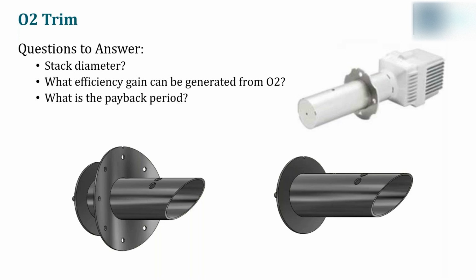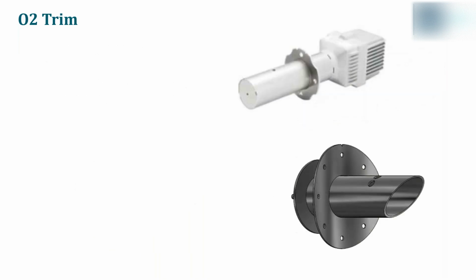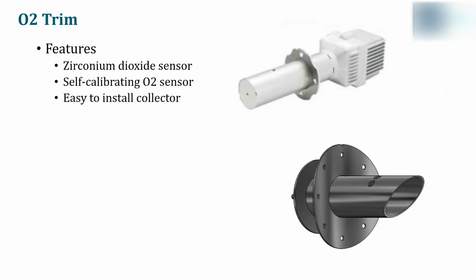This is all dependent on the size of the burner, the average operating load, average operating time, and current fuel costs, which all play a large role in how quickly the customer can expect to recover the cost of the O2 trim system. Now, for sizing purposes, all one needs to know is the stack size. There are only 2 options offered for the collector in terms of size. Some of the features include a zirconium dioxide sensor, a self-calibrating O2 sensor, and an easy to install collector.